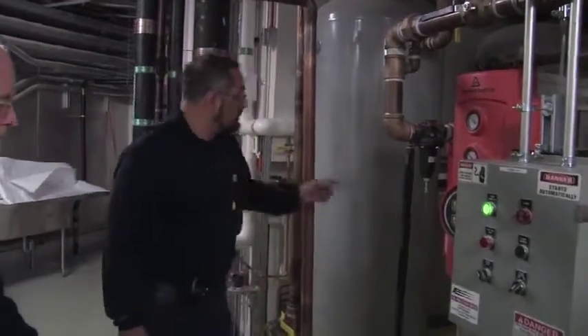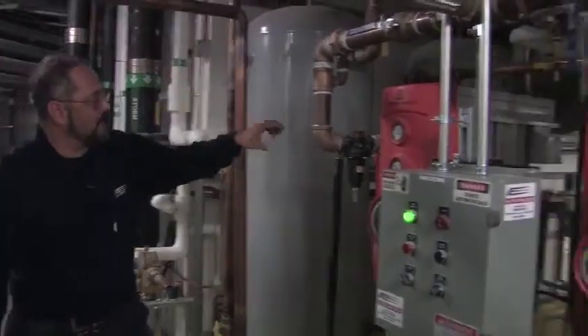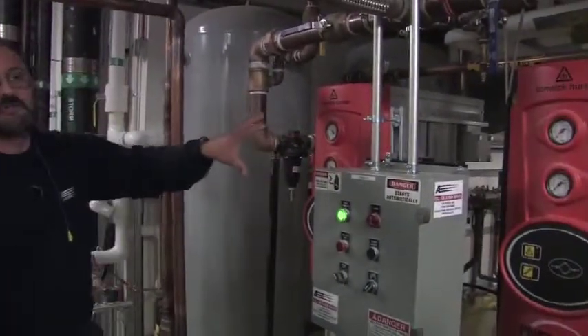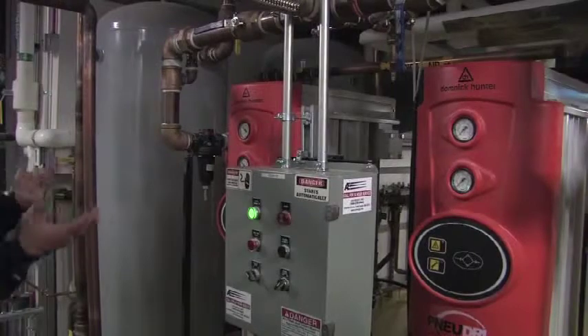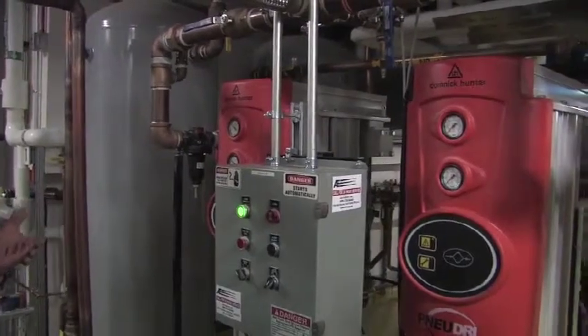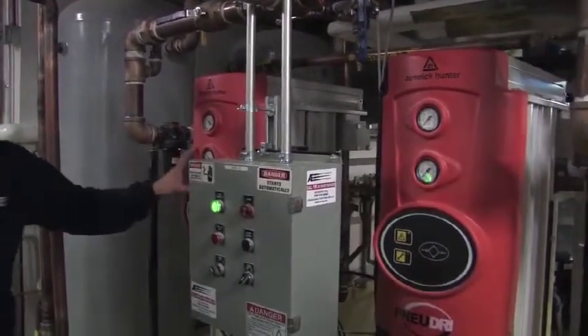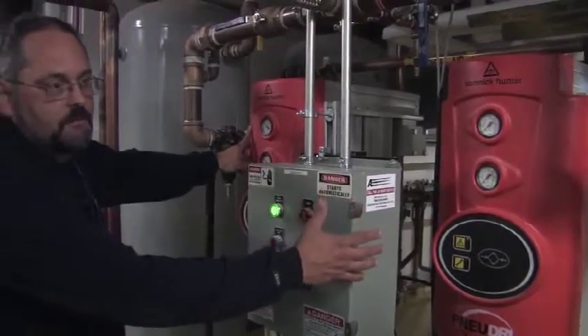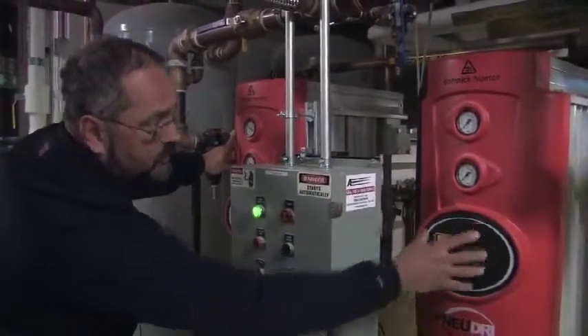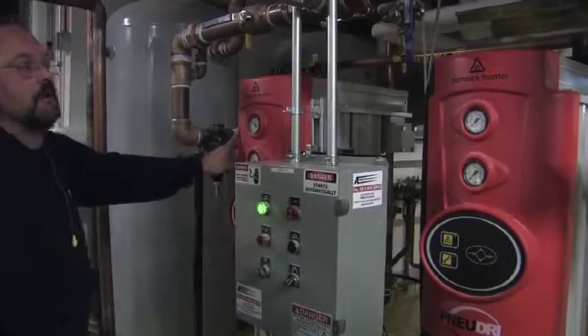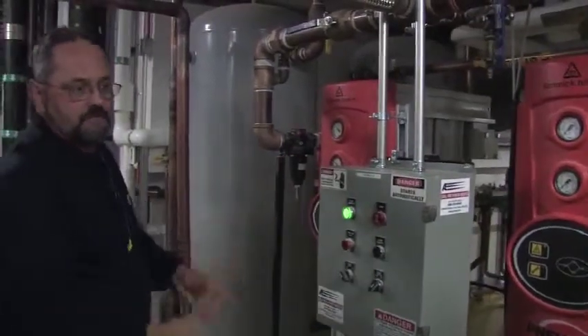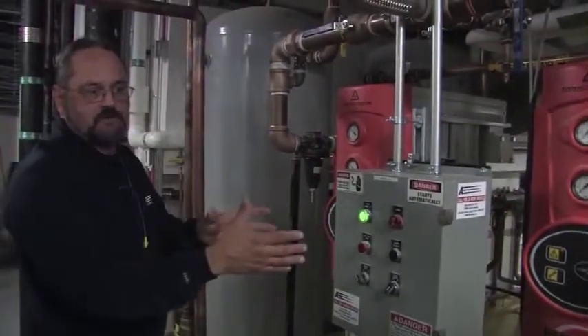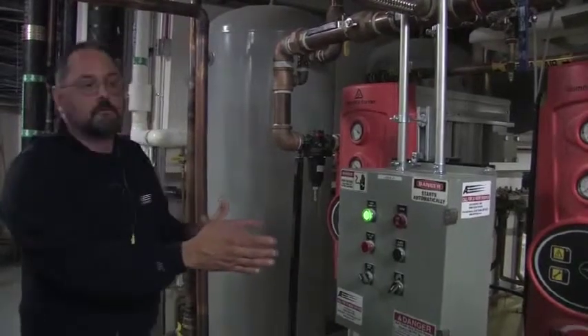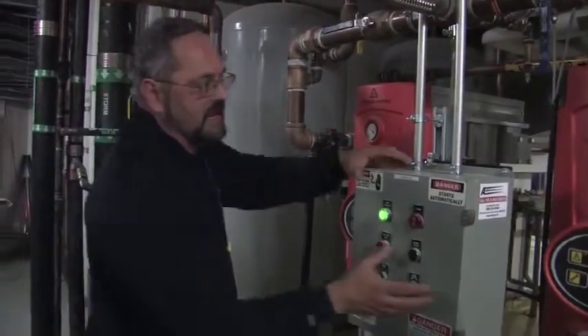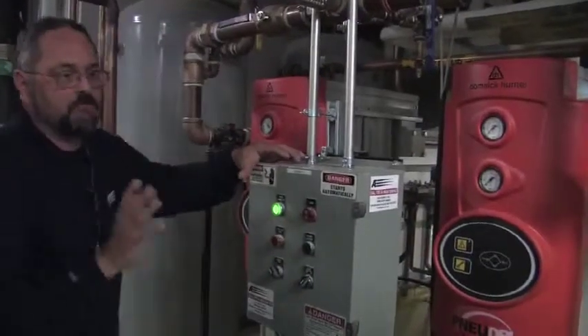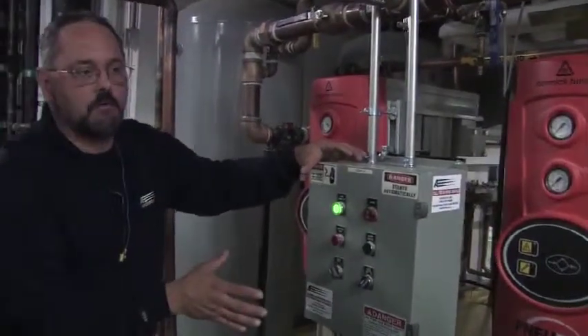So you get your two wet tanks. Air comes from that, goes to two dryers in tandem. Now these are set up to work the way the code says they should. We've got one on and one in reserve. So the one in reserve is turned off, powered down, and valved off. By being powered down and valved off, it should be as dry as it was when we shut it down. The internal system in here should be bone dry just like it was when we shut it down.